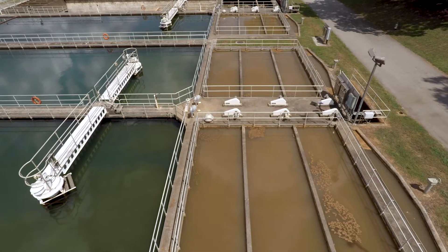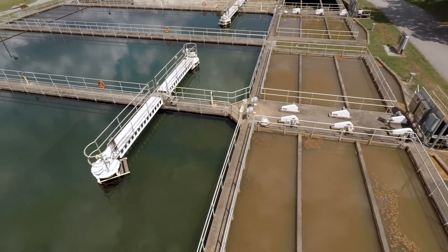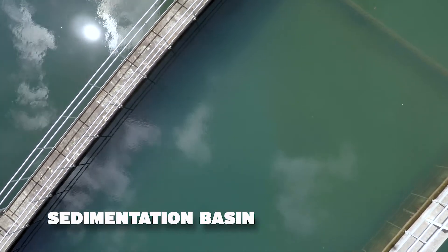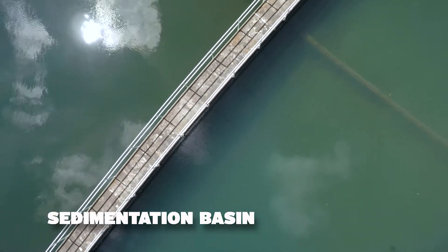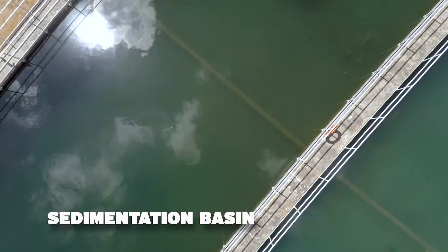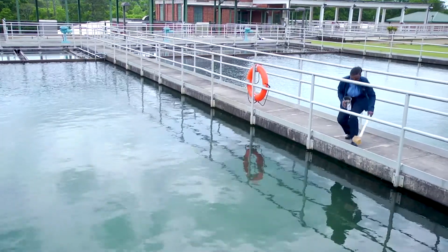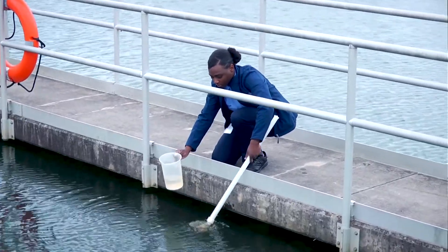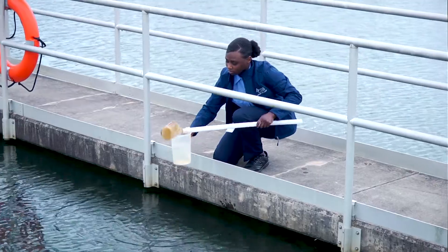Floc isn't the prettiest stuff in the world, but it's mainly just dirt particles. From the flocculation chamber, the water then flows into the sedimentation basin, and this is where things really start to settle down. In the sedimentation basin, the water is kept very still for about four hours. The floc is heavy, which means it will sink to the bottom of the basin where it's slowly pushed out with a sludge sweep. At this point in the process, we've removed any large particles from the water. The water is looking good and clear, but we still have a few more treatments to do before this water is ready to drink.